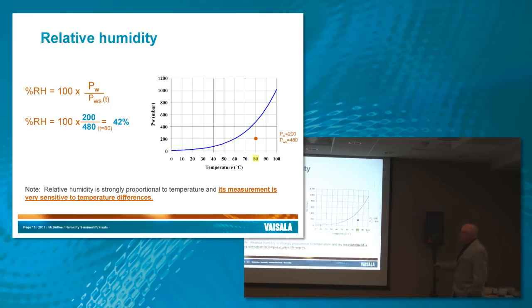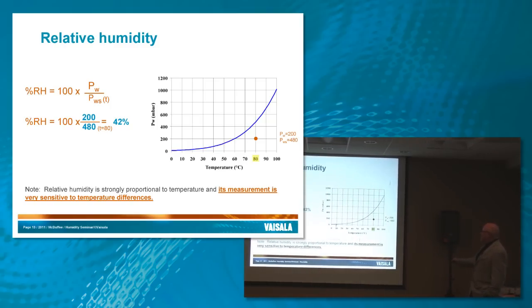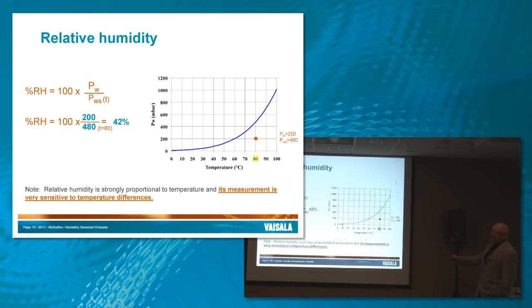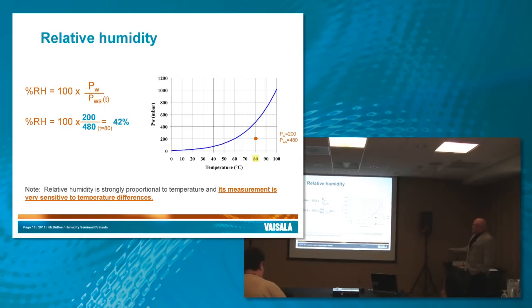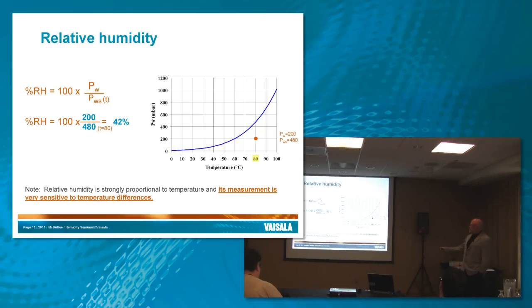But again, it's important to note that as the temperature changes, PWS here changes. So if you don't have a stable temperature, if your sensor is measuring relative humidity and you don't have a stable temperature, this keeps changing. And if this keeps changing, your measurement is going to be off. And we'll talk a lot more about that in the best practices section.